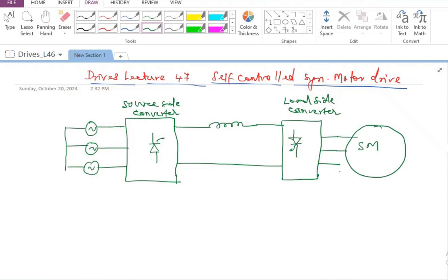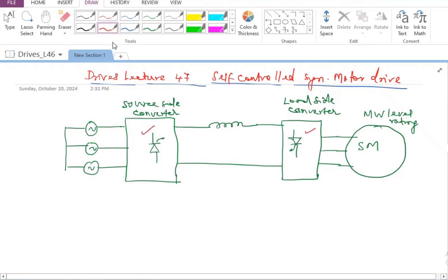So this is how the entire system looks. Now we said already that this will be of megawatt level rating in most cases. Because of that, and because we have a thyristorized converter here as well as a thyristorized converter here, if I try to look at the power quality on the source side, it is going to be pretty bad. Normally we will have fifth and seventh harmonics quite a bit.